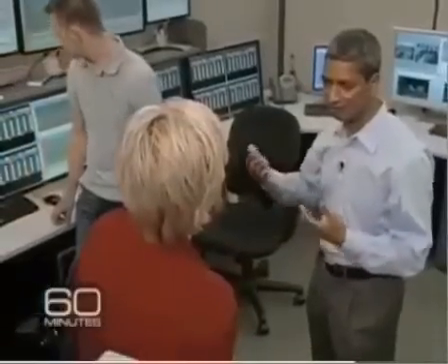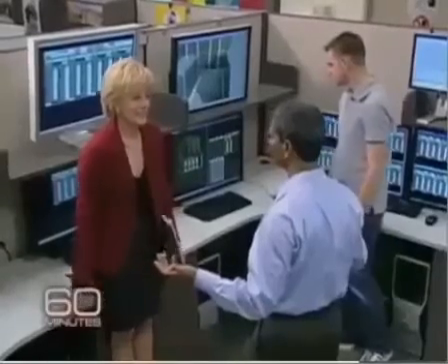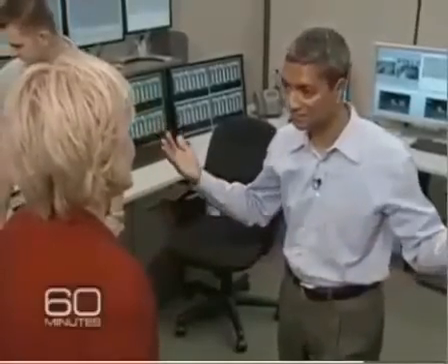KR told us that 3 weeks in at Google, suddenly one of the boxes just stopped. Your heart just drops. Did you panic? For a short while? Yes. He fixed that, then there was another incident. The air filters clog up and air is not coming into the system because the highway is kicking dirt. You just flip the system around and the problem is gone.